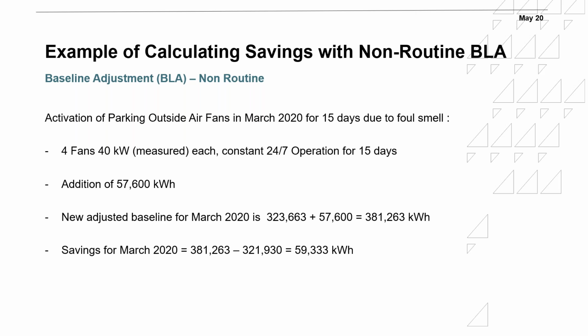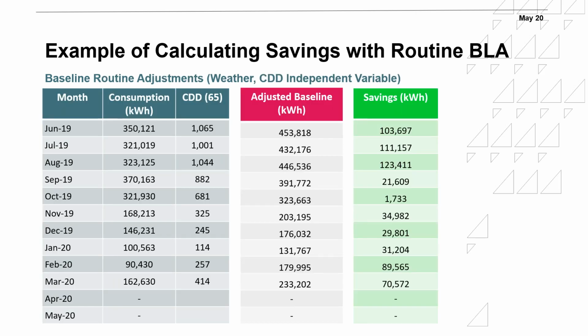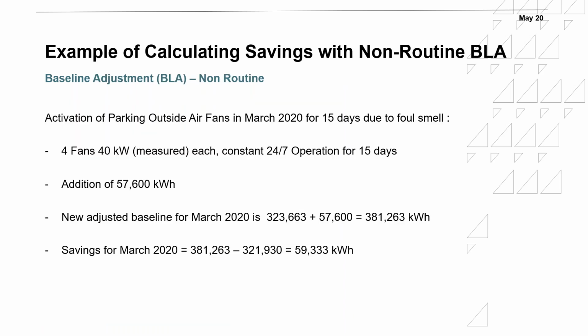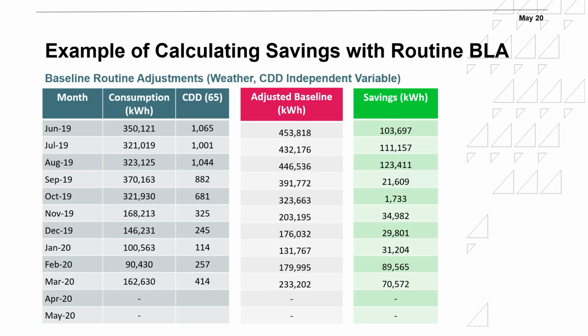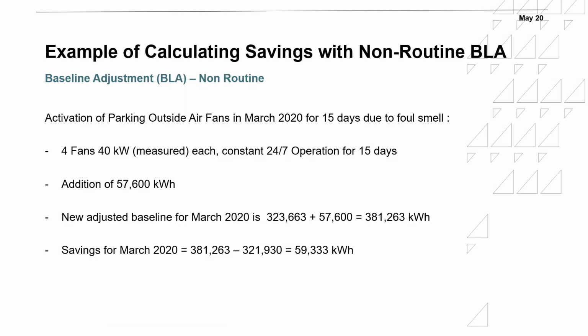And this is where I calculate the savings. So the new adjusted baseline is equal to 323,663 plus 57,600 that is due to the running of the fans for 15 days. That would be the new adjusted baseline. And then my savings, and sorry, this is not March 2020, it should be October 2020, is equal to the new adjusted baseline minus the reporting period consumption, and that will give me the savings. So this is what we call a non-routine adjustment.